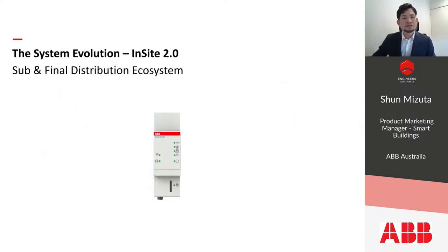Let's look into the InSite 2.0. The control unit is 2 modules wide, like this. If you want to measure the current or energy of the final sub-circuit of an MCB, you add this ribbon cable. Then you can add current sensors. We have solid core current sensors or open core current sensors. If you also want to connect the auxiliary contacts of the MCB, we have a smart auxiliary contact, which connects directly to the ribbon cable.